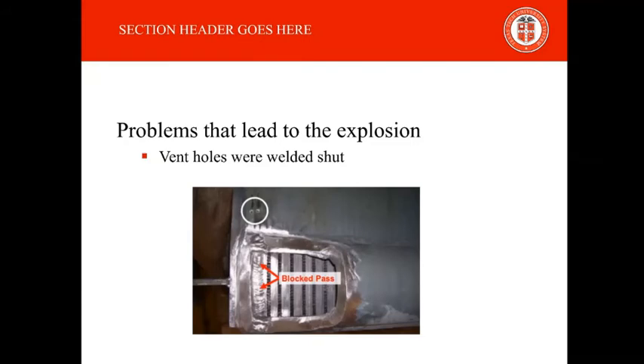Sometime between the repair of the brazed aluminum heat exchanger and 205 days of operation before the incident, the vent holes were blocked on the layers that had been welded closed. Without open vent holes, the blocked layers had no means to relieve pressure if a hydrocarbon leaks into them through a thermal fatigue-induced crack. On the night of the incident, when the unit was warmed up, the increase in temperature of the exchanger caused hydrocarbons to enter the blocked layers and become trapped. This caused a buildup of pressure and led to the eventual catastrophic rupture. The failure to leave vent holes to prevent pressure buildup is the third reason the catastrophic rupture was able to occur.